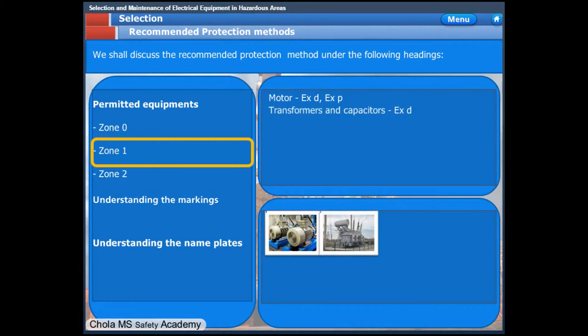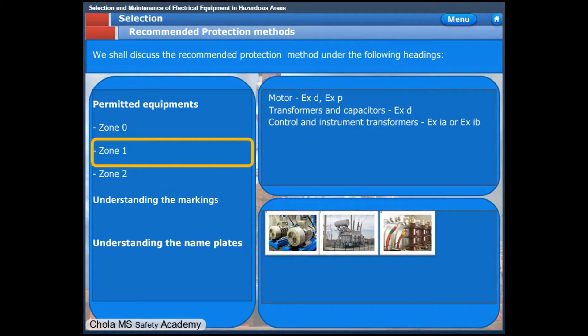Transformers shall be avoided as far as practicable in hazardous areas, but if unavoidable, transformers shall be flame-proof type. The same applies to capacitors. Control and instrument transformers shall be intrinsically safe, Ex ia or Ex ib type only.